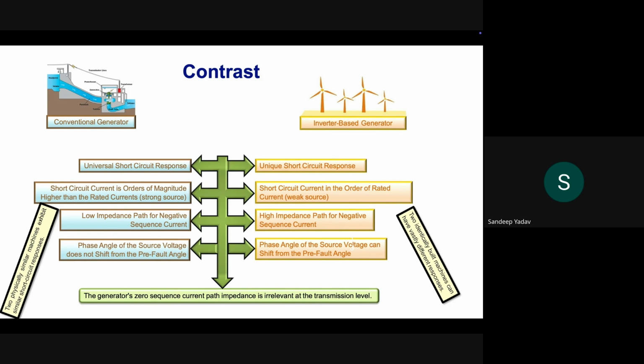So we had the comparison of a synchronous machine with an inverter-based resource. We can see that in terms of short circuit response, the conventional generator will have a universal short circuit response. It is predictable in nature. More or less, it will be the same for all the machines. However, the short circuit response of an inverter-based resource may vary from manufacturer to manufacturer. The short circuit current in a conventional generator may be multiple times its rated current. It may go up to 6 to 10 times the rated current of the machine.